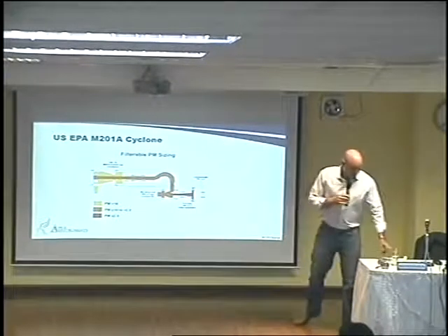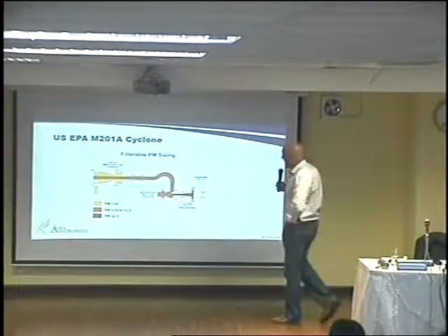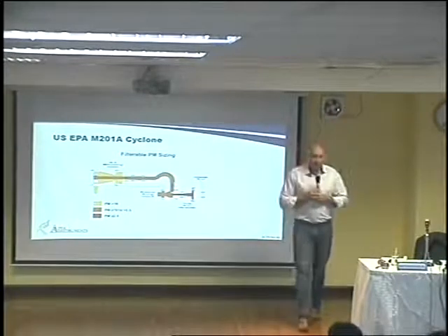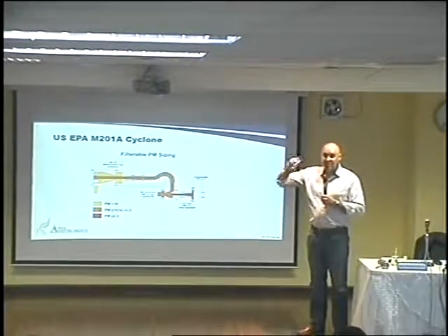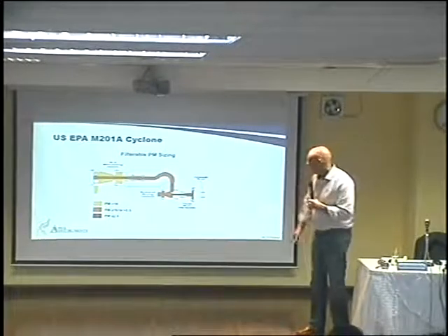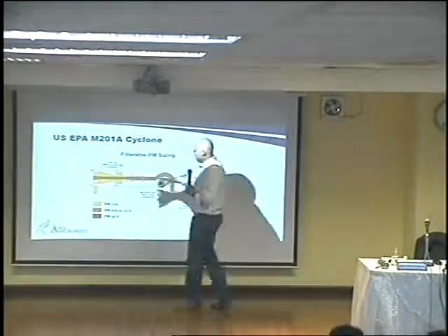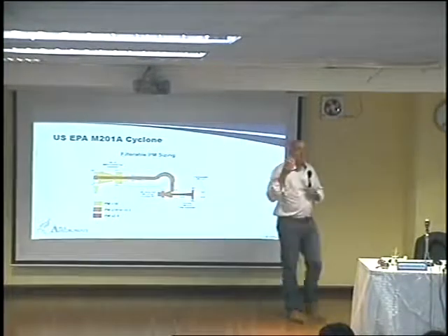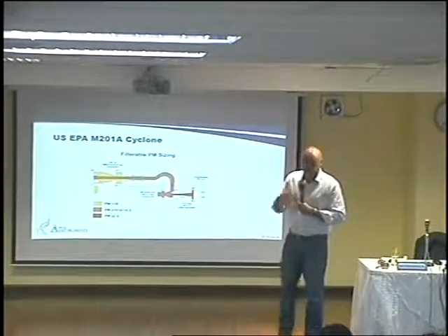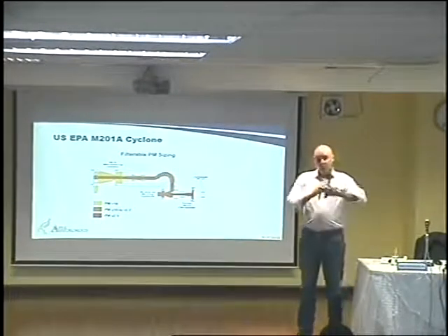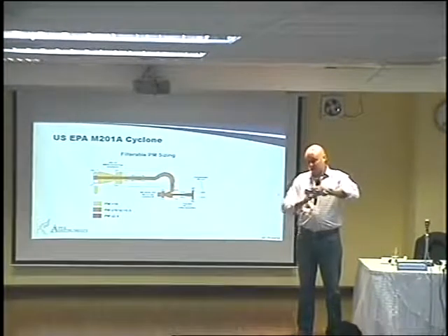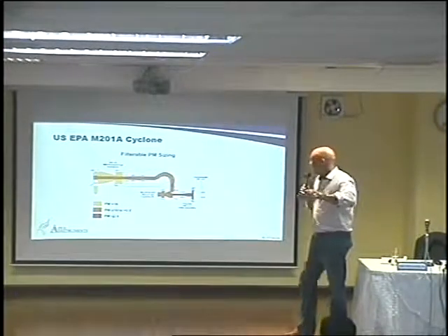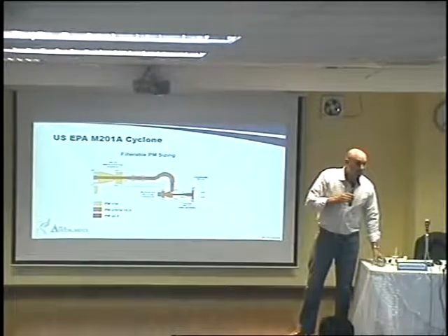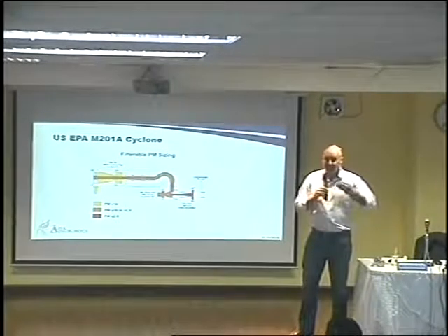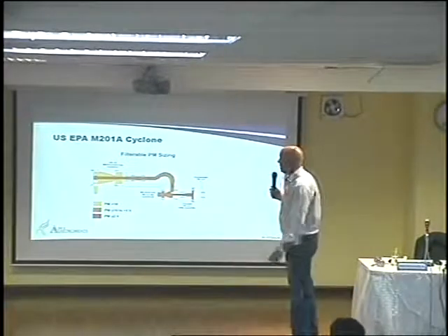So this is a really valuable slide here. It shows how the flow of the PM goes and where it actually sits within this instrument, okay? So everything here in the yellow captures our particle size bigger than PM10, okay? So that's inside of our cyclone, around the outside here, and inside our nozzle. So we're going to do that as a recovery separately and account for that as everything larger than PM10.